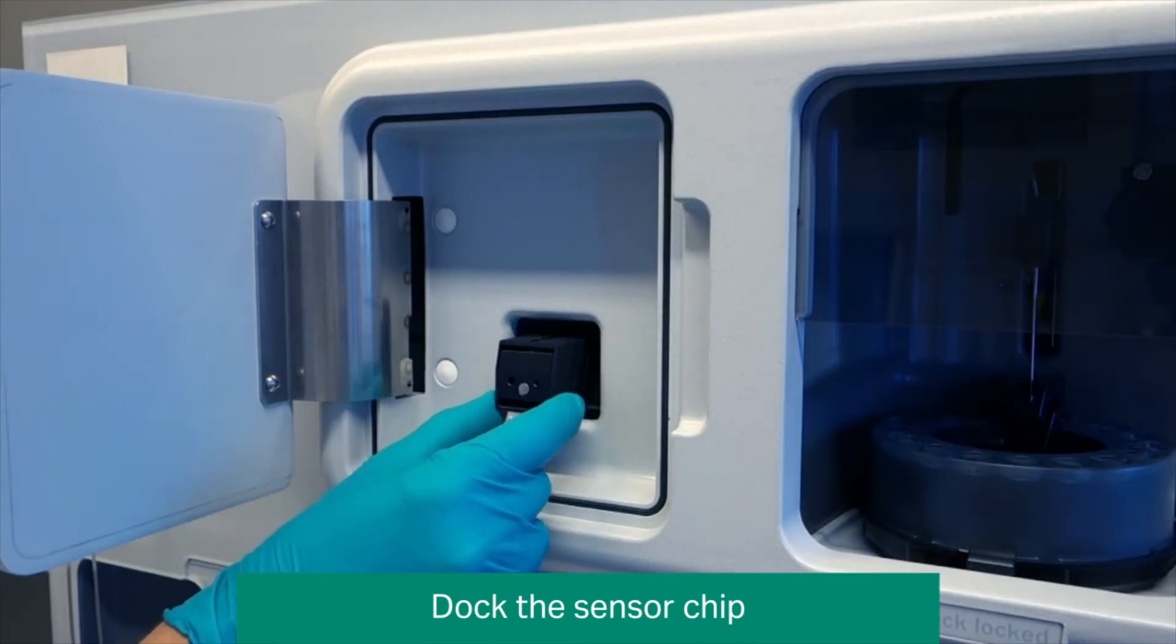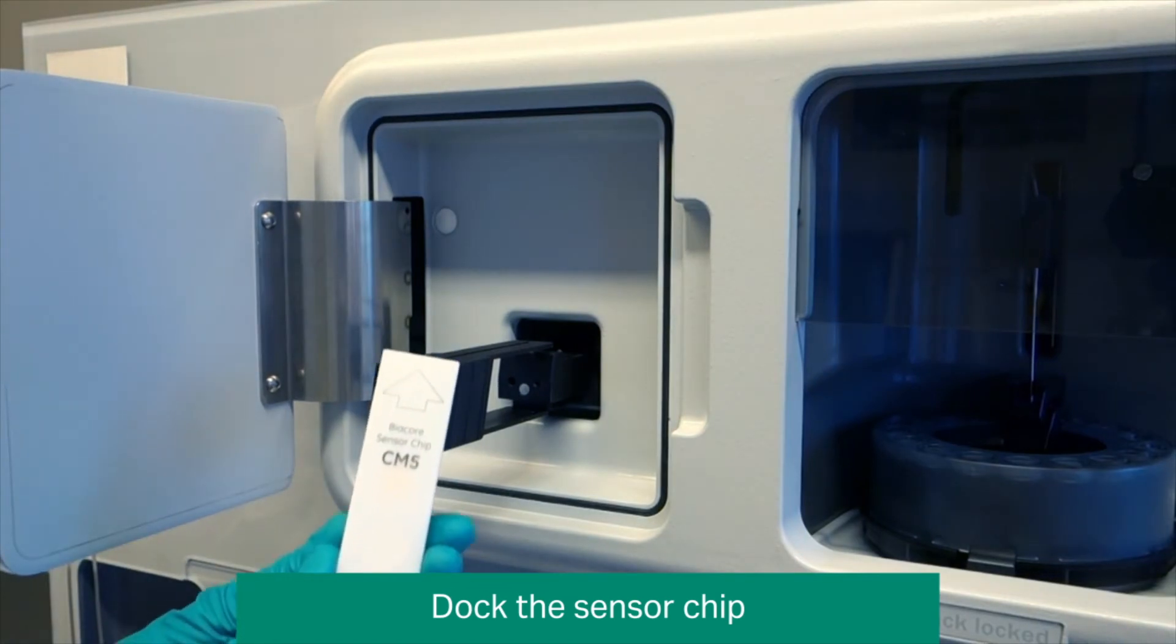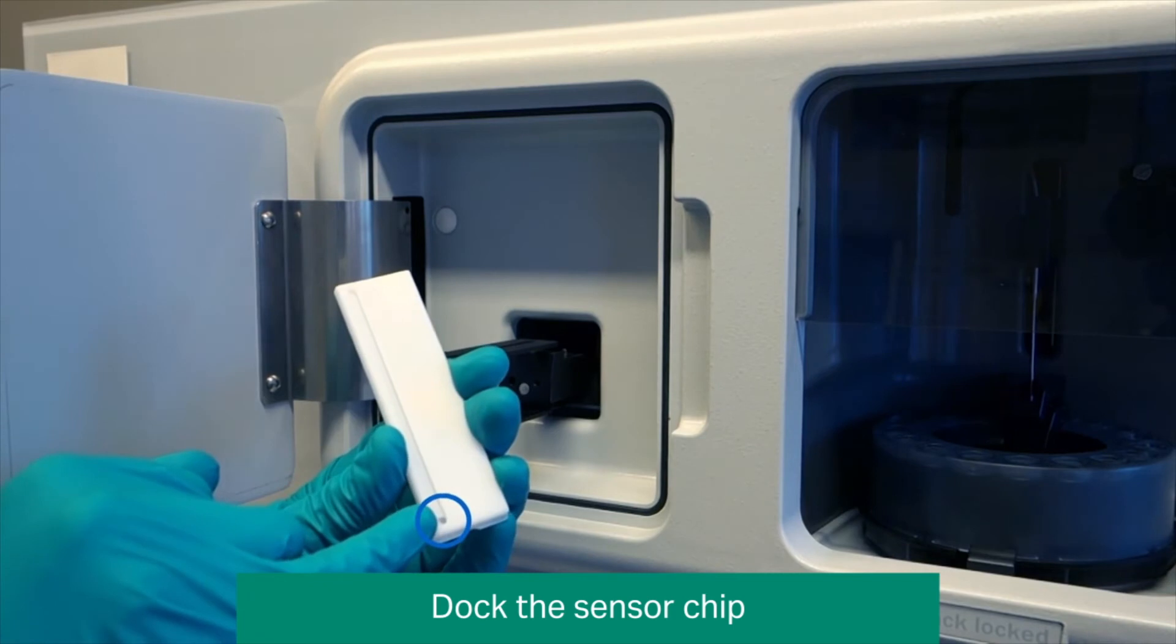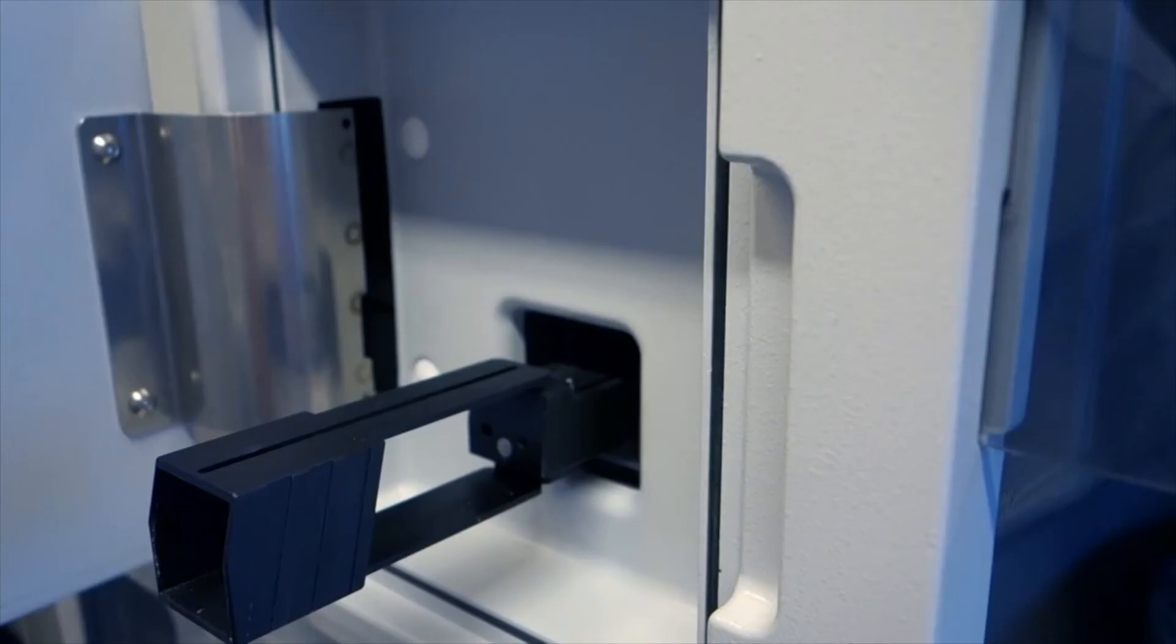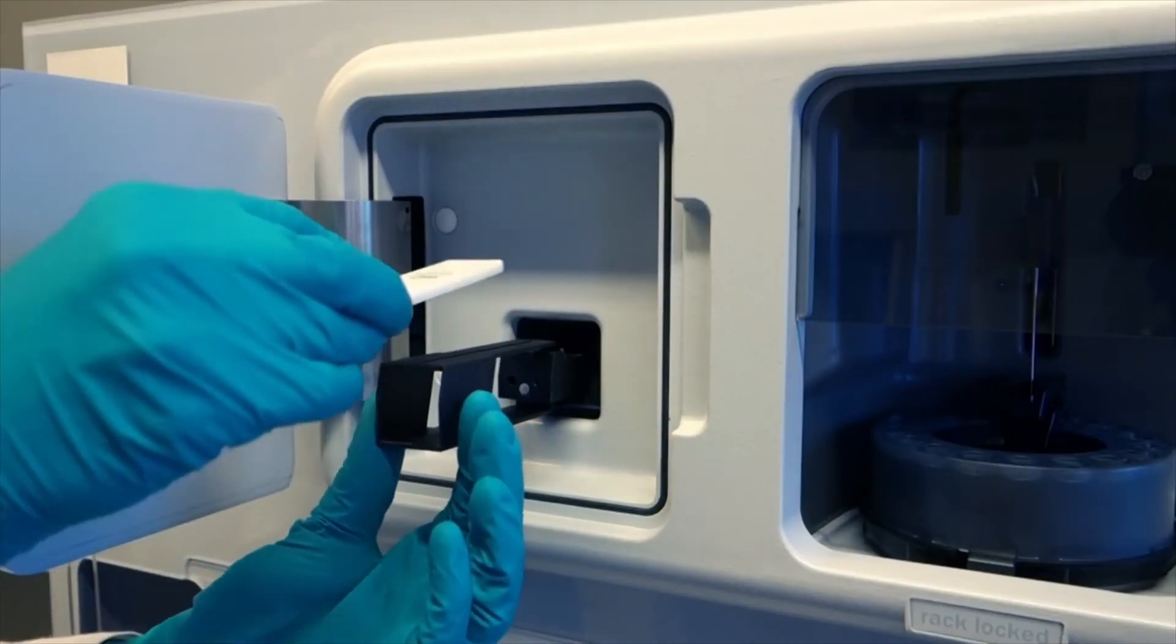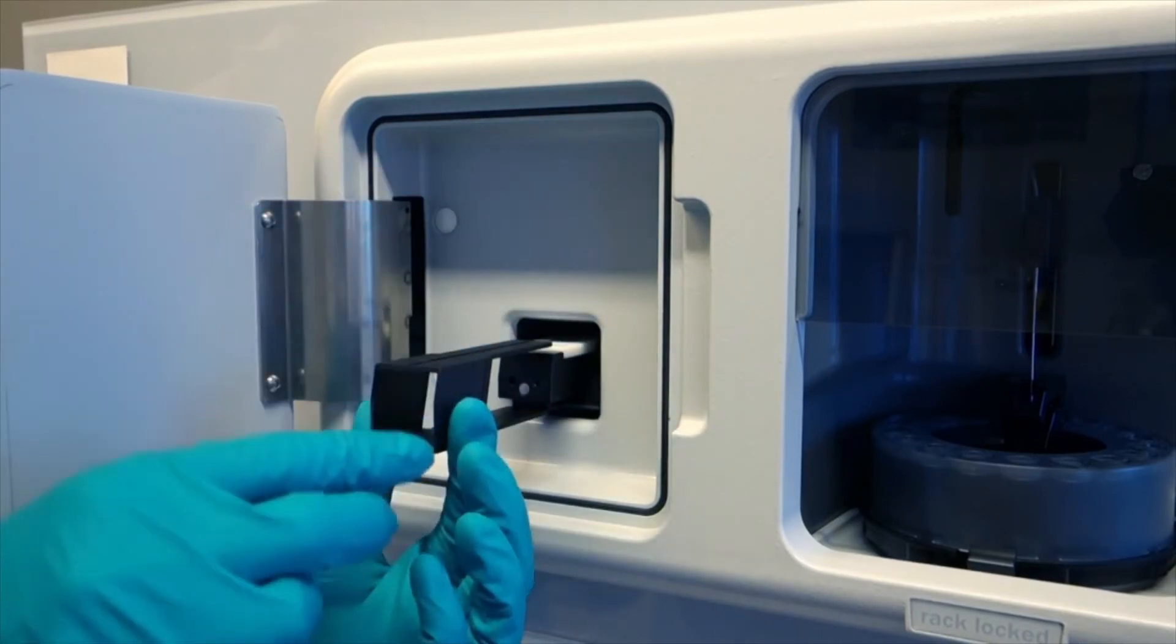To dock the chip, pull out the chip slide. Notice the hole on the underside of the chip carrier and notice the pin. Insert the chip with the text on the upper side and the arrow facing the instrument.